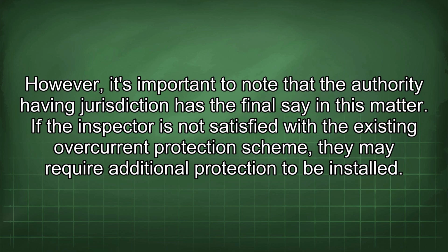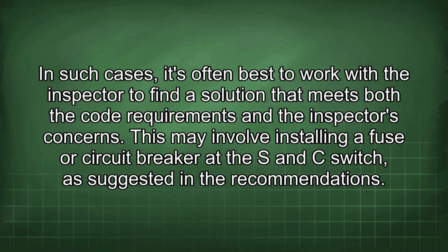However, it's important to note that the authority having jurisdiction has the final say in this matter. If the inspector is not satisfied with the existing overcurrent protection scheme, they may require additional protection to be installed. In such cases, it's often best to work with the inspector to find a solution that meets both the code requirements and the inspector's concerns. This may involve installing a fuse or circuit breaker at the S and C switch, as suggested in the recommendations.